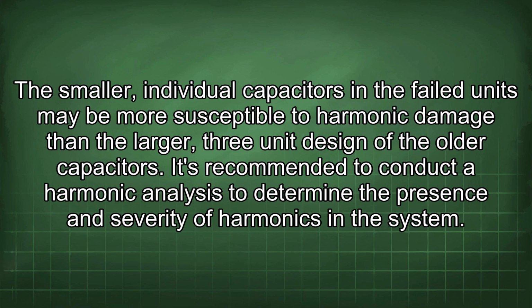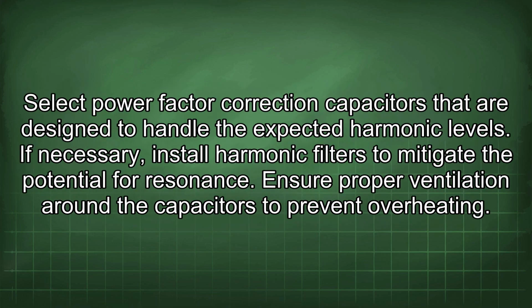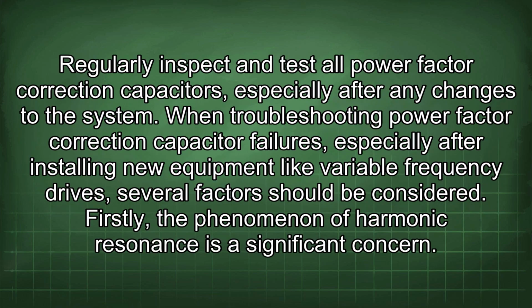The smaller, individual capacitors in the failed units may be more susceptible to harmonic damage than the larger, 3-unit design of the older capacitors. It's recommended to conduct a harmonic analysis to determine the presence and severity of harmonics in the system. Select power factor correction capacitors that are designed to handle the expected harmonic levels. If necessary, install harmonic filters to mitigate the potential for resonance. Ensure proper ventilation around capacitors to prevent overheating. Regularly inspect and test all power factor correction capacitors, especially after any changes to the system.